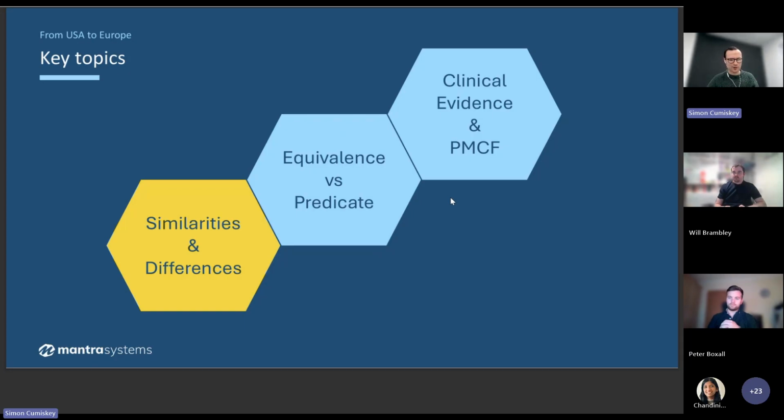Like I said, different notified bodies work in different ways, and that includes the timelines that they work to as well. It varies depending on device, but there are some notified bodies that can do software as a medical device certification in 6 months. And there are other notified bodies where their typical time to certification can be all the way up to 18 months. Now, it depends on the device type and the relationship that you have with them.